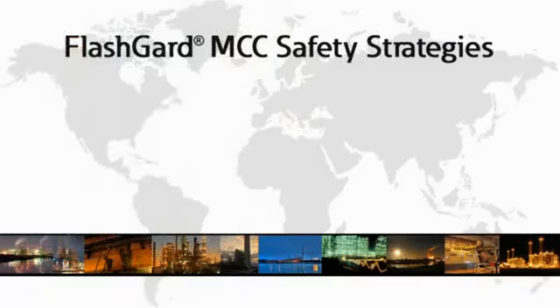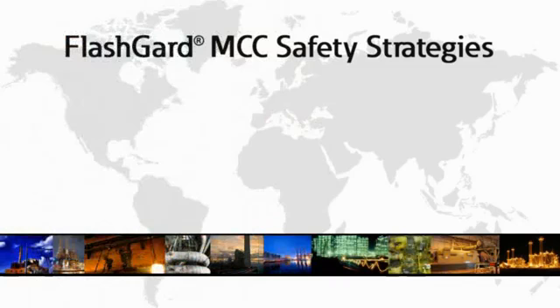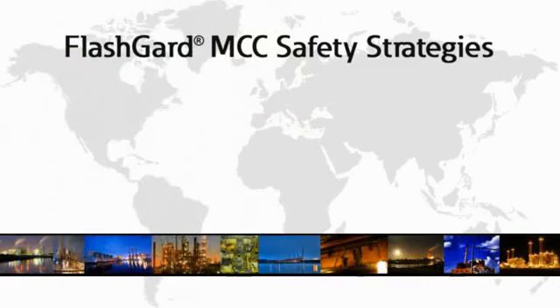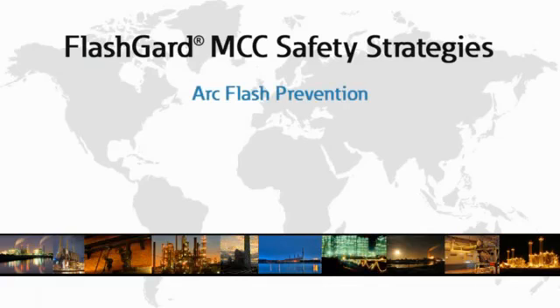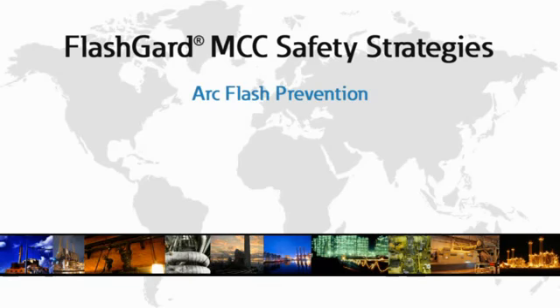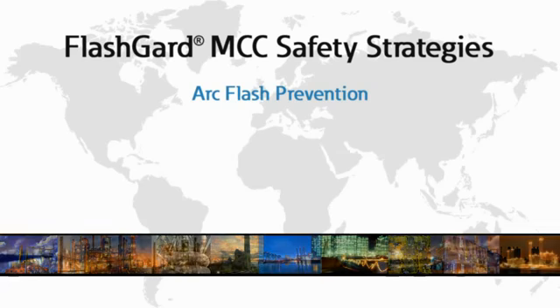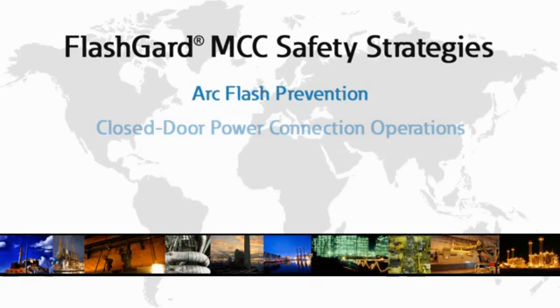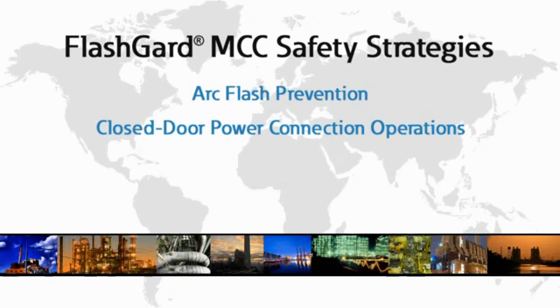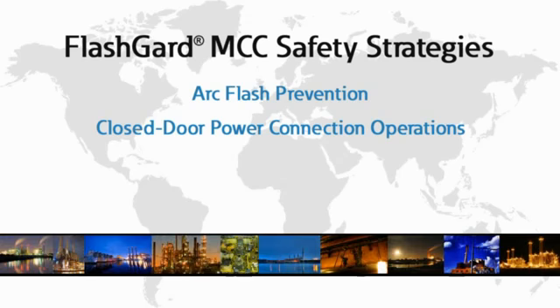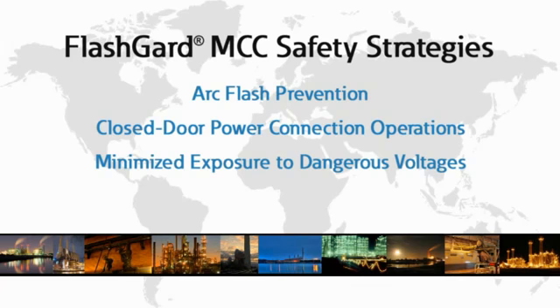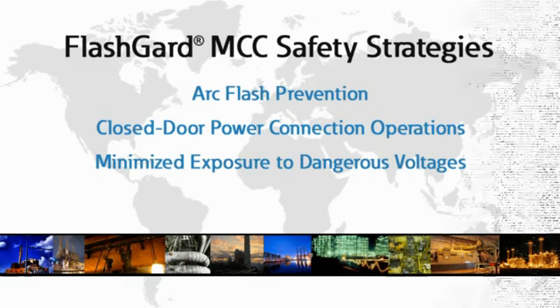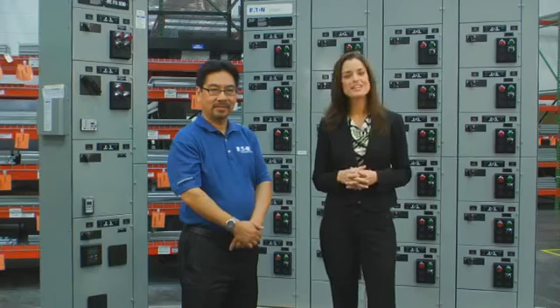FlashGard was the industry's first low-voltage arc-preventive motor control center and was designed to minimize the likelihood and severity of arc flash events. In particular, the FlashGard MCC addresses three key strategies to maximize equipment and operator safety: prevention of arc flash events through insulation and isolation of assembly elements that are prone to incidental arc flash occurrences during maintenance, a design that allows units to be disconnected and reconnected from the vertical bus with the door closed, and minimized operator exposure to dangerous voltages. To show us how these strategies work in practice, we're joined today by Ed Yee.